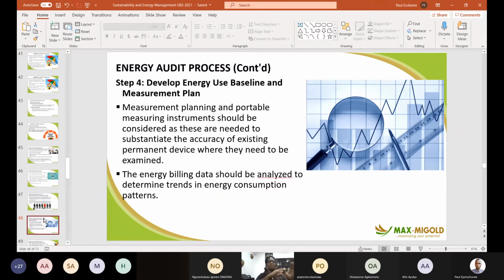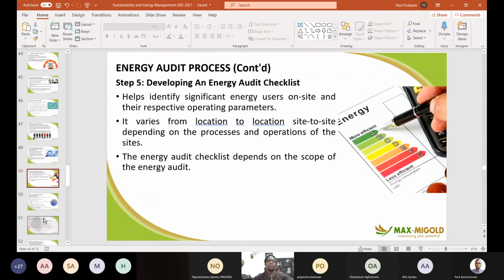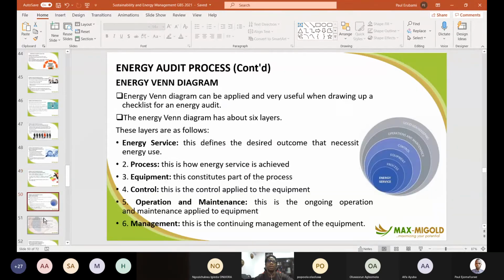That's why you need an energy management system with continuous, real-time recording, so you can get your averages, your peaks, and your lowest readings from the data. Then you create your energy audit checklist, identify significant energy users, and note their operating parameters. You want to focus on the biggest energy consumers in your facility—that's the main attraction, because if you can identify wastage in them and save, you definitely feel fulfilled and accomplished.